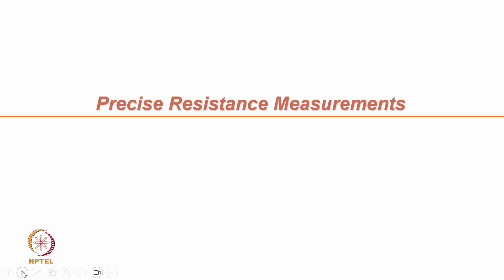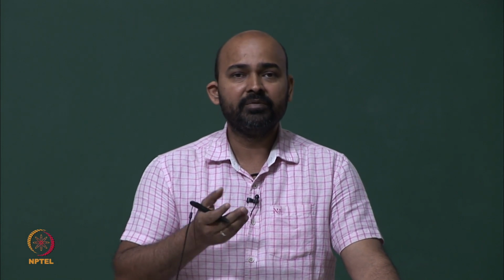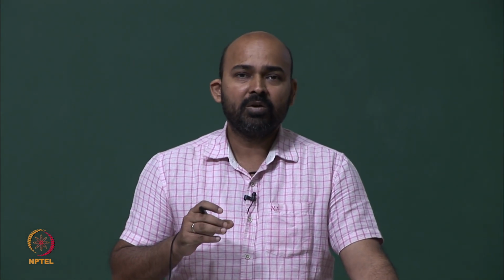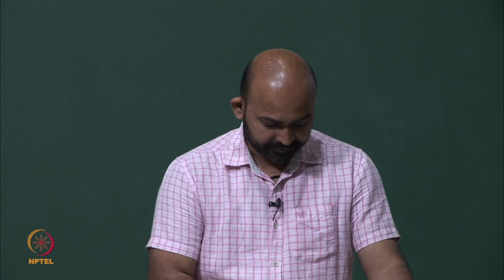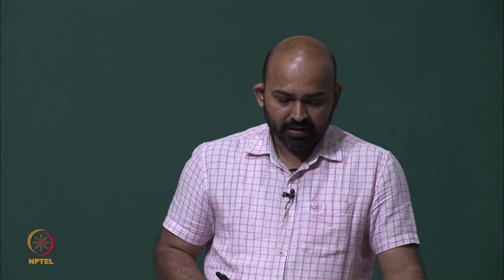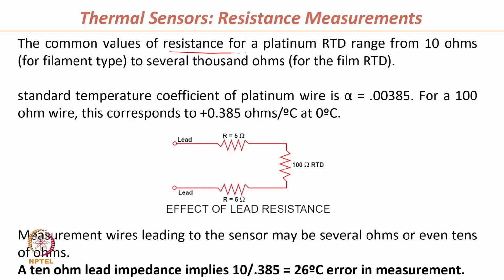So, now we come to how we do the measurement using these RTDs. We have these RTDs which are fabricated using thin film. They are very small in size. Now, how do we take measurement of temperature using these RTDs? So, the common values of resistance for a platinum RTD range from 10 ohm to several thousand ohms. These are the typical resistance values of RTD, 10 to let us say 50 kilo ohm.